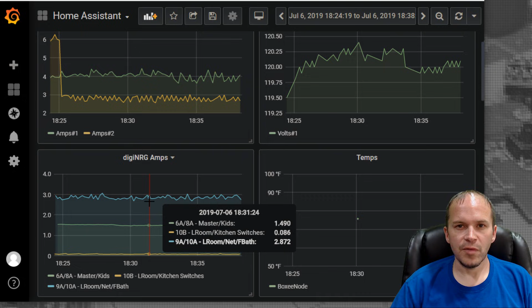I have one lighting circuit holding steady at 0.29 amps. If I turn this dimmer on, you'll notice the percentage isn't much, and it's just 3 simple LED bulbs over the table. Now you'll notice we went up a tenth of an amp on that lighting circuit. We'll jump to halfway and go up to 0.36. We'll go to full brightness and jump up to 0.44, and you'll notice it's holding steady as well. It's not jumping around, there's no noise, and we're back down to almost our original level of 0.29, where we started.